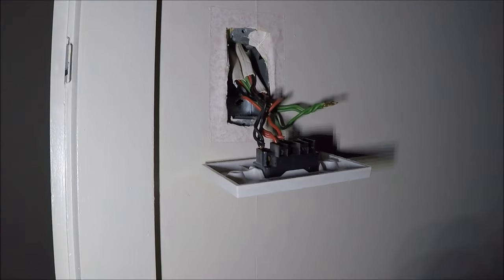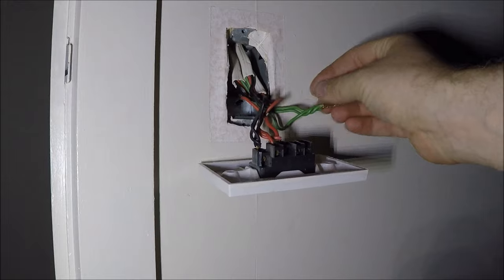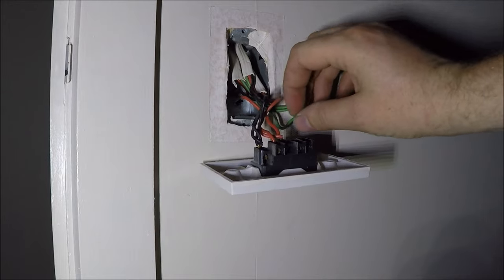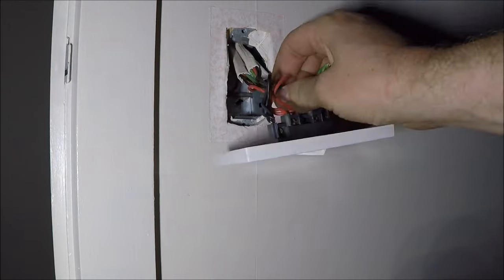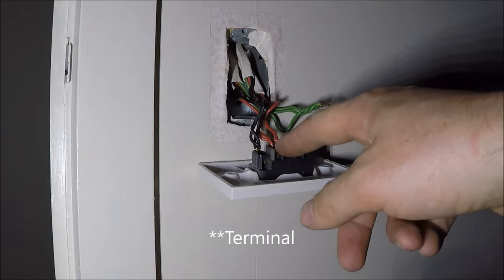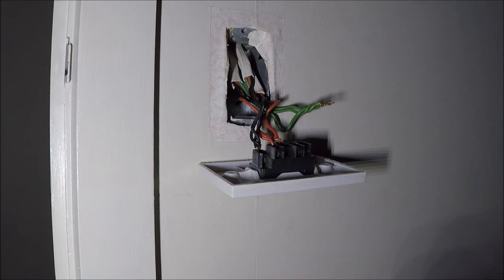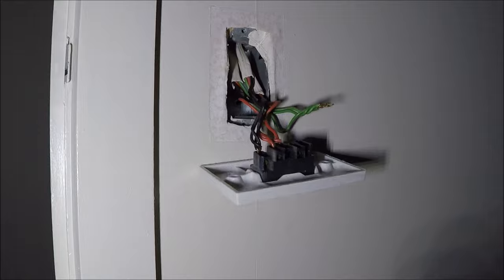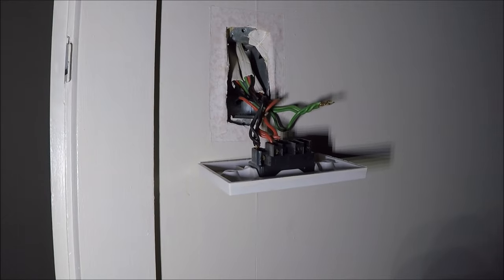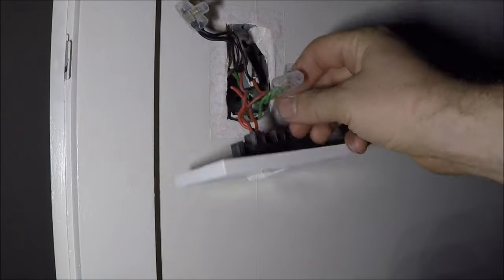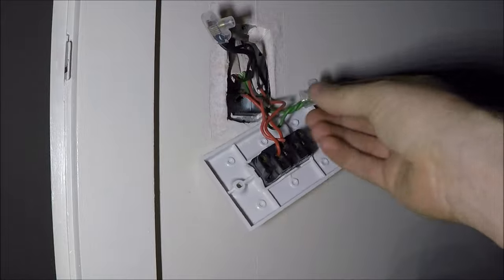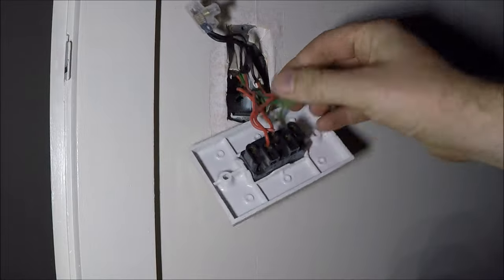If you do come across cables that are green and black and have a bit of red sleeving on them, make sure you note down what switch they came out of and copy that onto the next one, because it means it's a two-way switch. So watch my two-way switching video if you want to understand that sort of stuff. This one here is a simple one-way switch. It's the only light in the room, so they're pretty straightforward. So as you can see, I'm throwing them into these connectors here. They'll get stuffed back in the box.